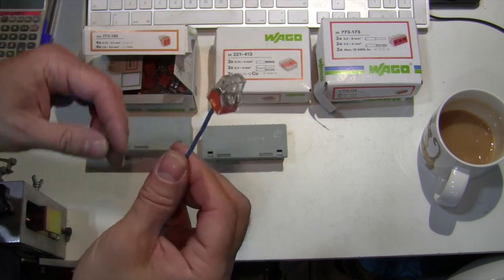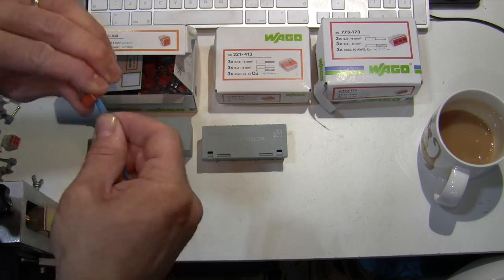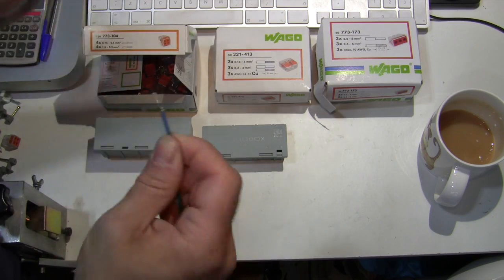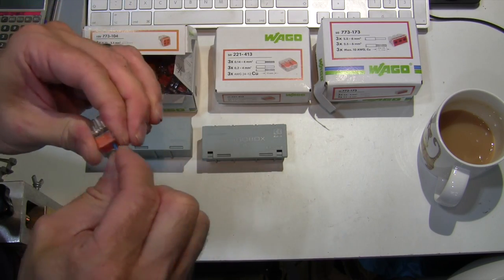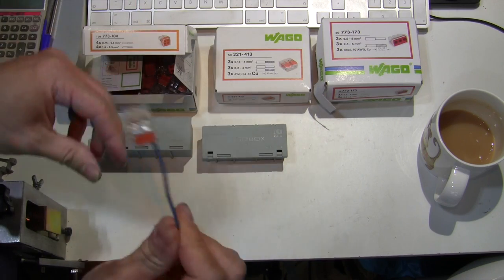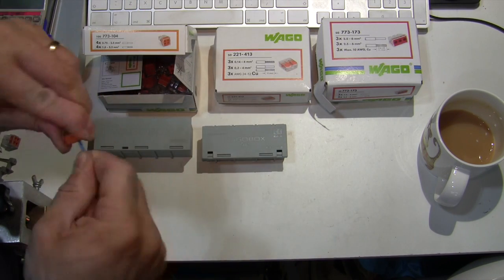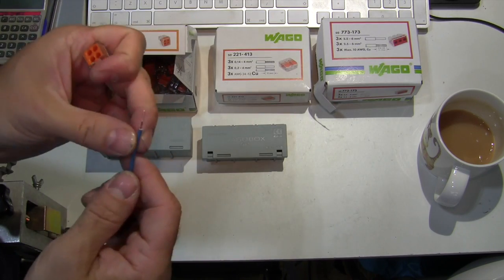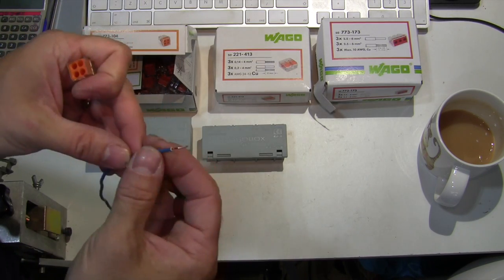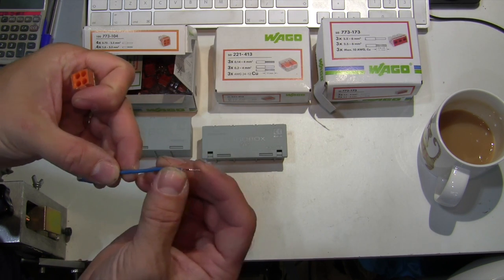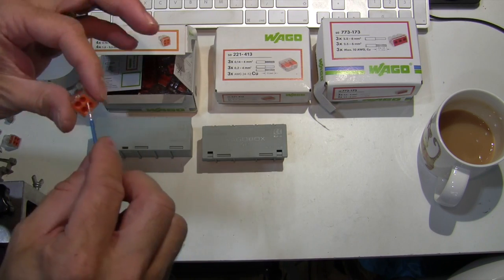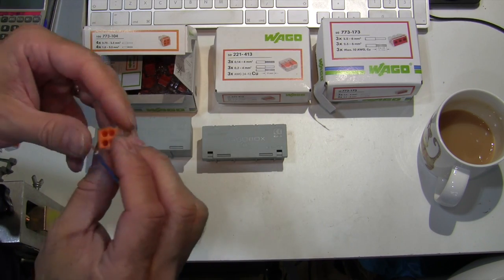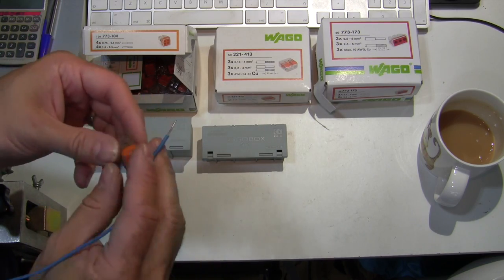Some people think that you can't get these back out again. They do actually make them so you can come out. It does take a bit of twisting, but it will come back out again. And that's still a perfectly usable connector. Still very strong as it goes back into the same hole there. Good product. I really like it. The only thing I would say is if you have twisted it to get it back out again, it's sometimes worth cutting and re-terminating the end, just to make sure that the copper there hasn't been nicked or weakened in any way. Because what you don't want to do is shove it in and have it break off, because then that is going to be impossible to retrieve the bit of copper that's left in there.